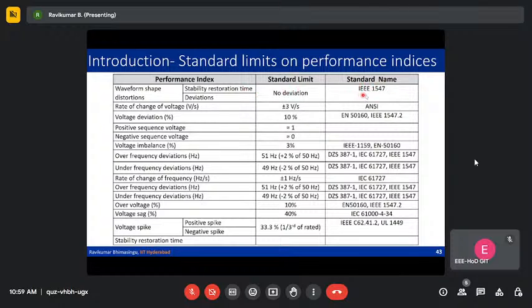This is as per the IEEE 1547 standard. There is one more thing, the rate of change of voltage, measured in volts per second, which should be limited to plus or minus 3 volts per second as per the ANSI standard. Voltage deviation, measured in percentages, should be limited to 10% as per IEEE 1547. For positive sequence and negative sequence voltages, we don't want any negative sequence voltages. We always want balanced operation, so positive sequence voltages, and voltage imbalance should be limited to 3%.